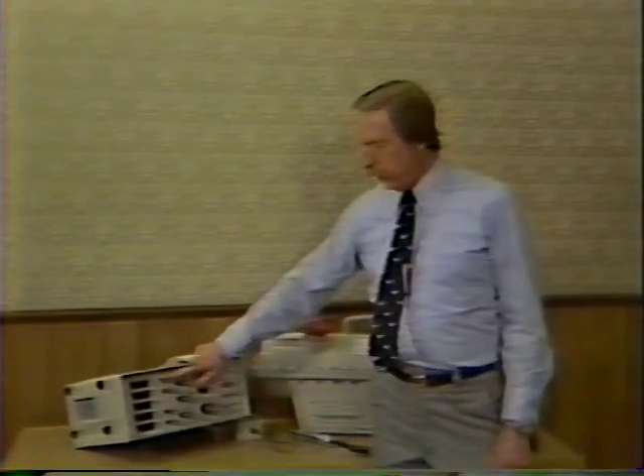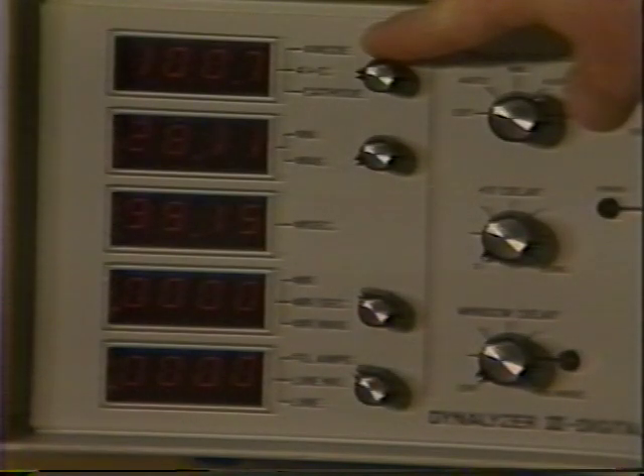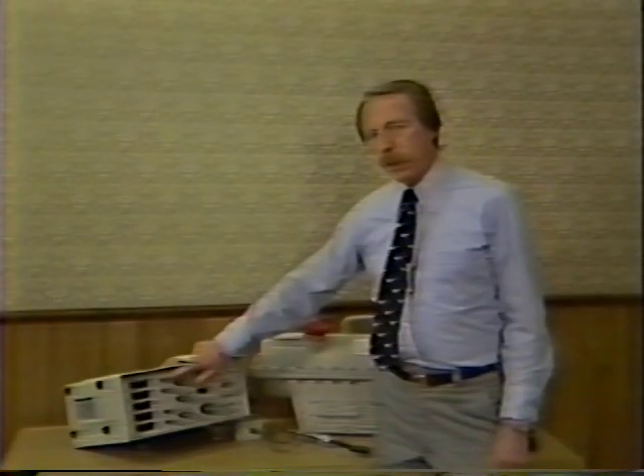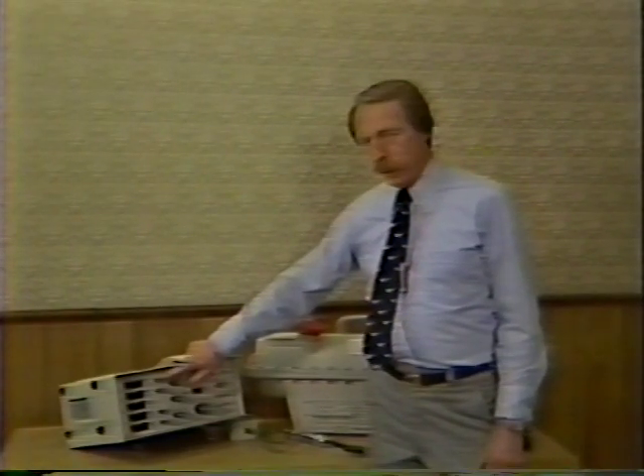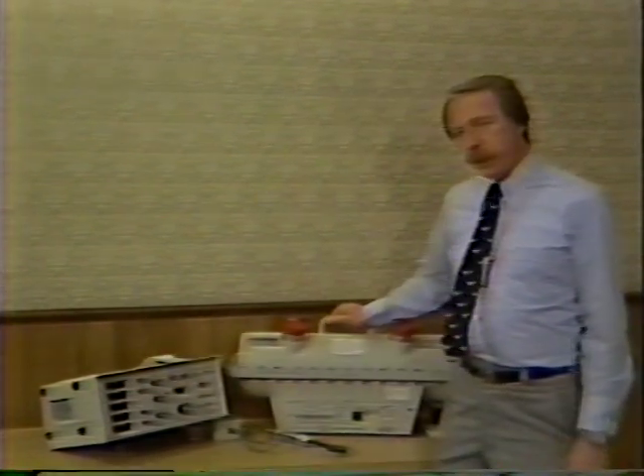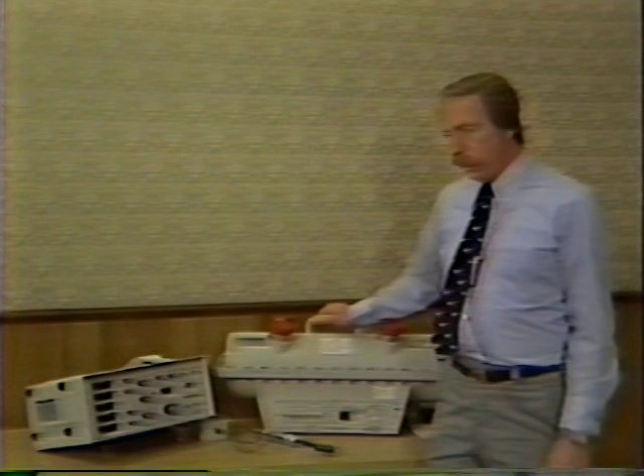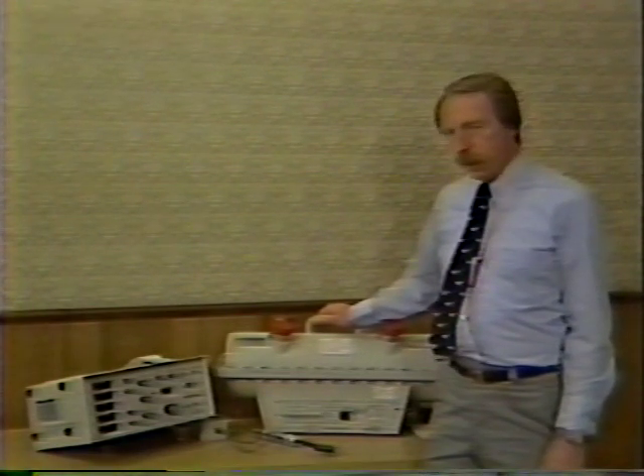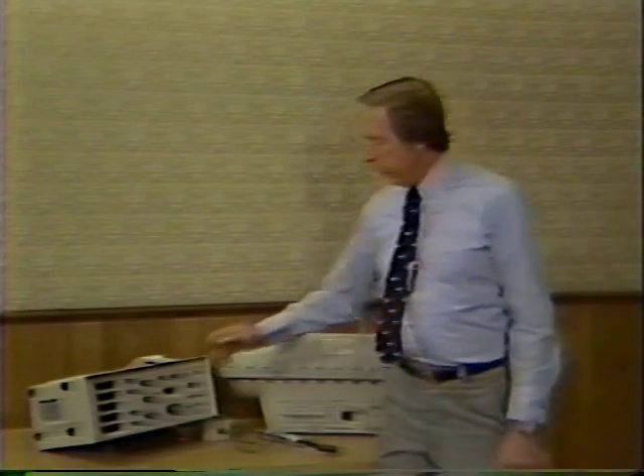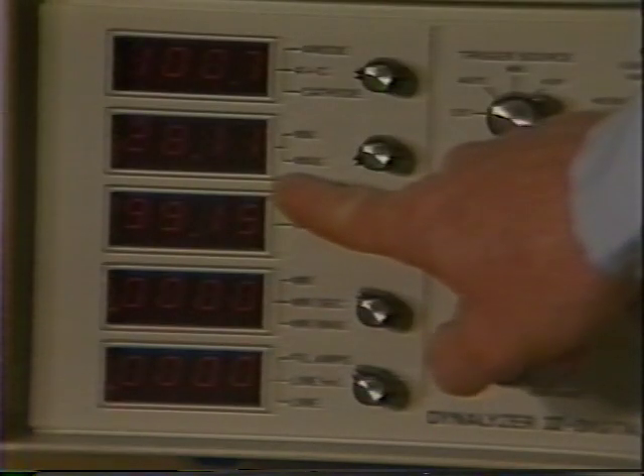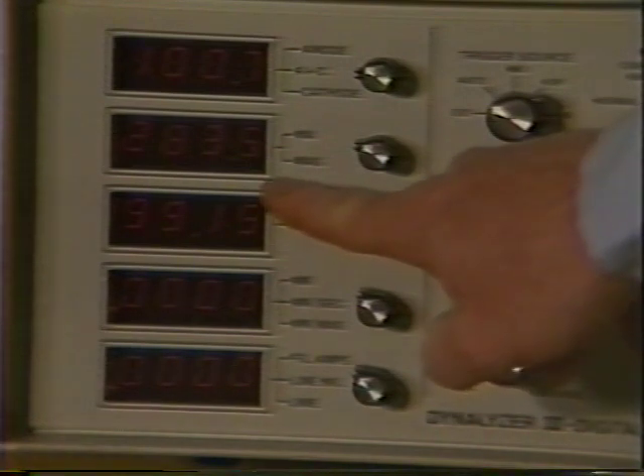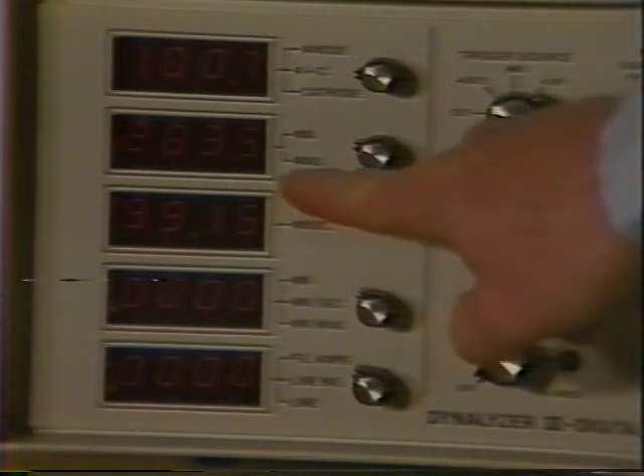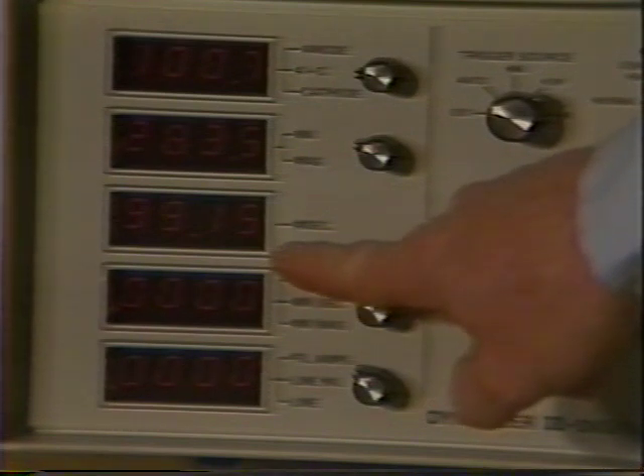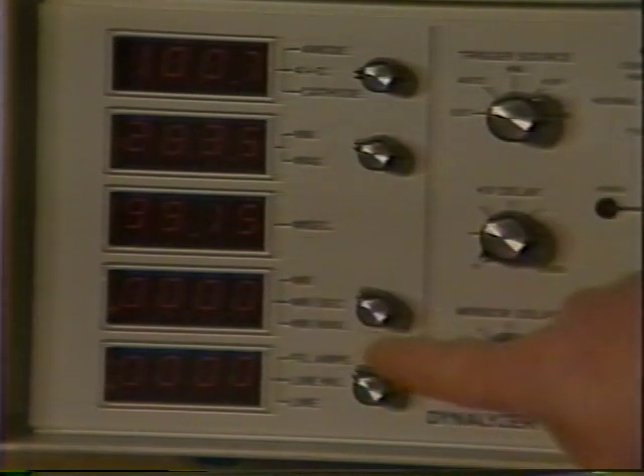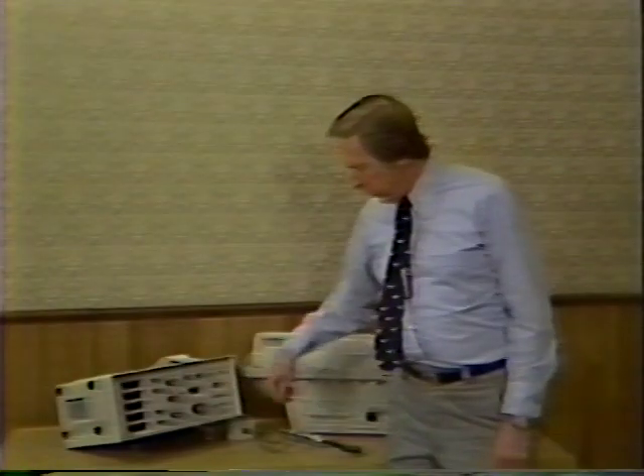On the top LED, we'll be reading summed kV, or anode plus cathode. Recall that we measure kVp to 1% accuracy, and the high voltage unit is frequency compensated to 100 kilohertz, which allows us to see spikes and transients that are not normally seen on other equipment of this type. On the next LED, we measure mAs; we divide by time and have mA available to us, both of which are stored. On the next LED, we'll be measuring time in milliseconds, and we'll hear more about that in a few minutes. On the next LED, we're measuring mR, or radiation, assuming we have the radiation probe in the X-ray beam.